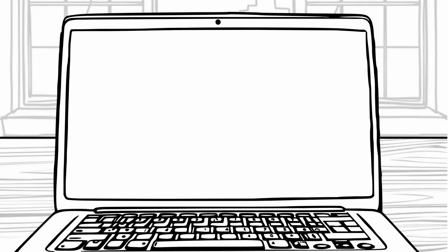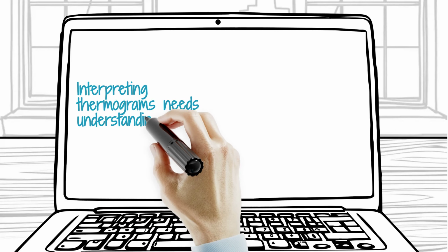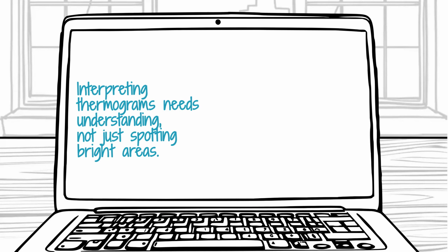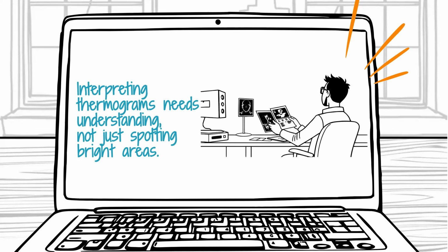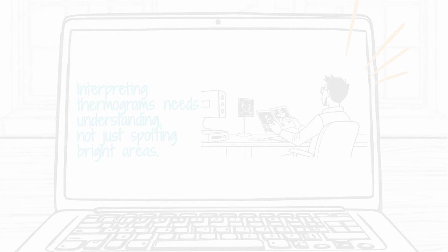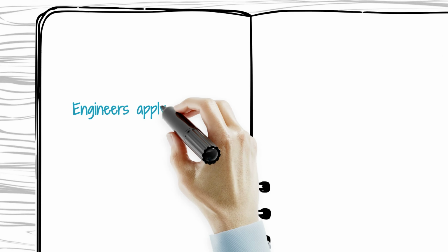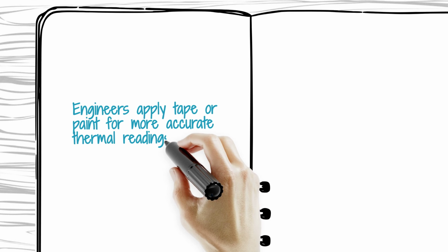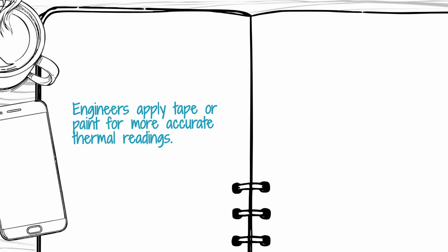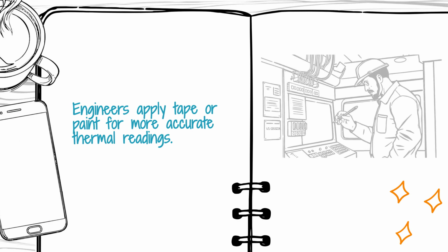Interpreting these images correctly requires more than just looking for bright spots on a screen. A skilled technician must understand the concept of emissivity, which is the ability of a surface to emit thermal energy. Shiny metallic surfaces like polished copper bus bars have low emissivity and can reflect the heat of surrounding objects, leading to false readings. To get an accurate interpretation, engineers often apply matte electrical tape or specialized paint to these surfaces to standardize the thermal data. When analyzing a thermogram, the most common fault identified is a loose or corroded connection.